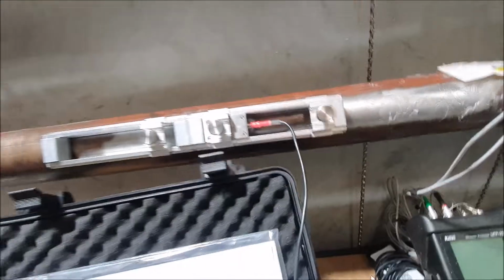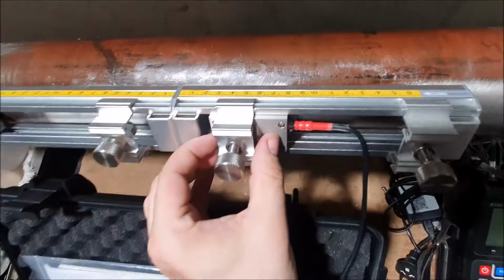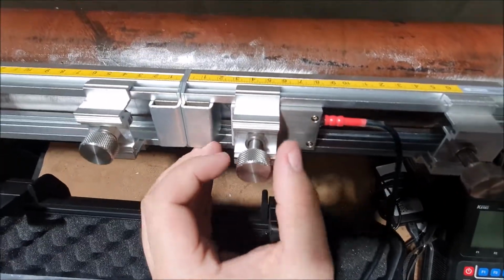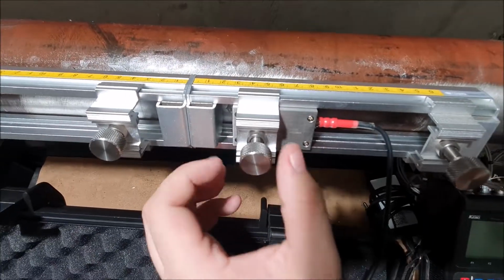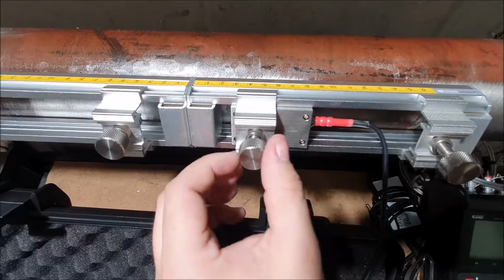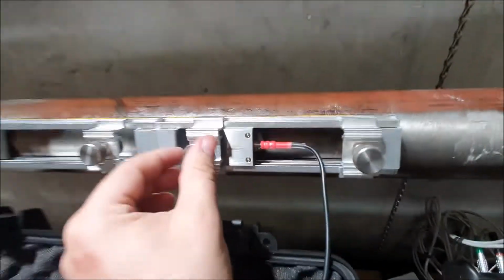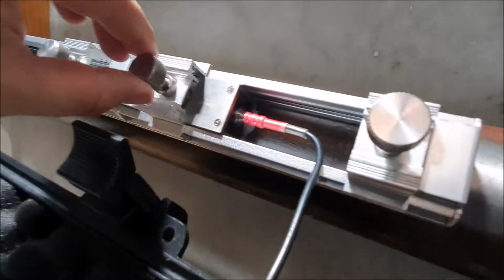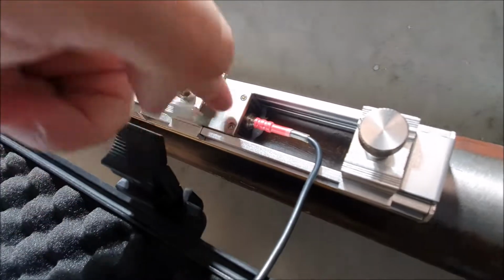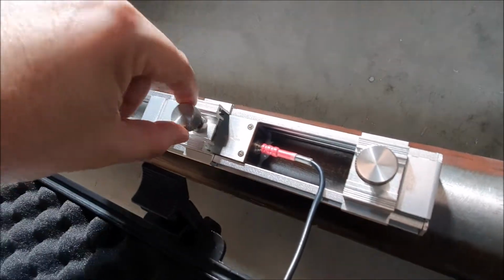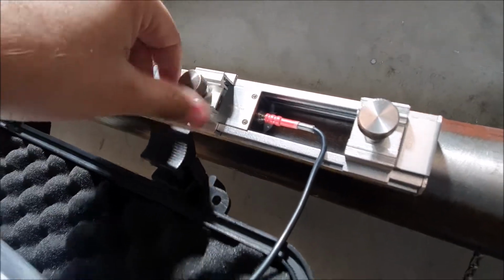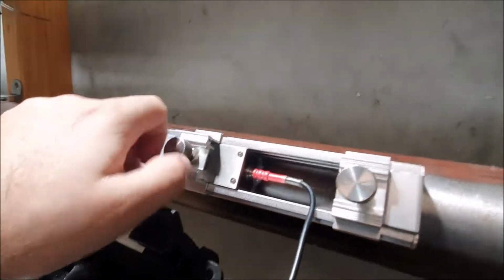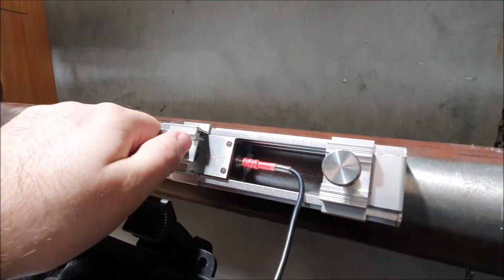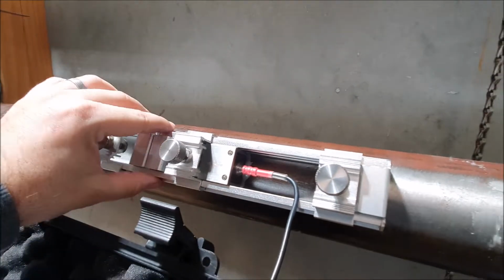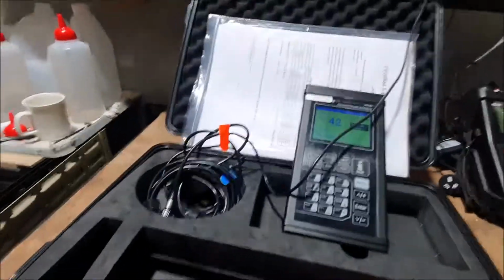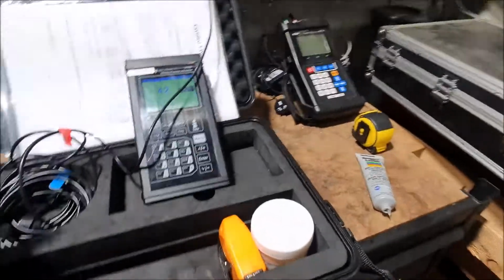But what we also want to do is say, let's go for 3 centimeters on this side, and then we can base the other side off that distance. And you'll see I'm just tightening this frame down, and that just tightens this transducer down onto the pipe. That's probably actually a little too tight. It's lifting the frame. Let's just make it snug. Okay, and we'll do the same over here on this other transducer.